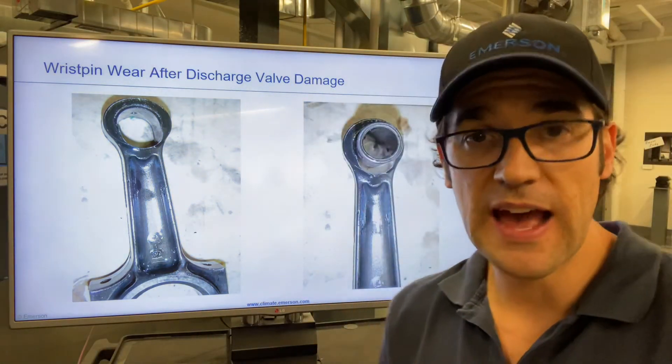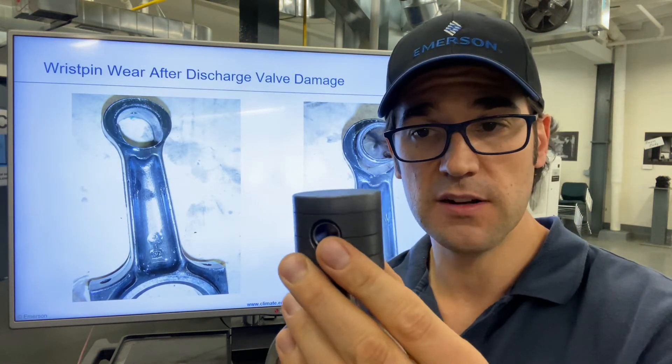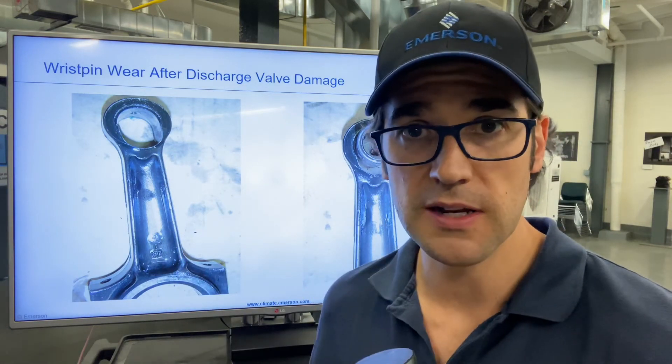And if this happens, how do you test? You pull off the pump, you get the piston to top dead center, maybe turn over a little, and just push down on it. If it drops and makes a noise, you have wrist pin wear. That compressor is going to need to be replaced.